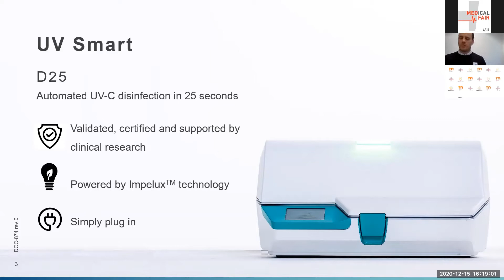We are powered by our patented and trademarked Impelux technology. I will get to that later, but it enables us to do very fast and rapid disinfection, validated at the same time. One of the advantages of our device, and of UV light, is that it's very simple to plug in. The only thing you need is a 220-volt socket, and then the device runs. So you don't need any special connections for water, chemicals, special power, etc. All you need is a normal plug.